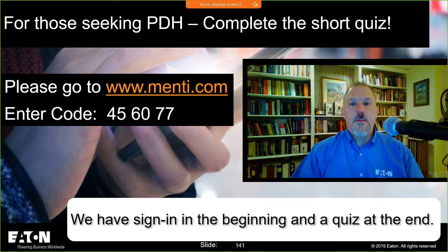Handle ties do not create common trip. That is correct. Thank you, Mr. Platt. Yep. No requirement to trip the second breaker. That is right, but it is a requirement to open it when you open it.